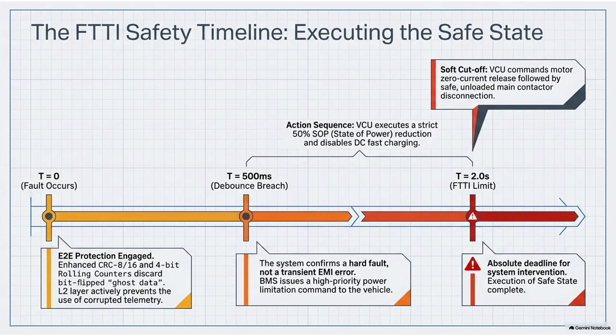Exactly. In milliseconds, the inverter stops chopping the power, and the massive river of current slows to a trickle and then hits 0 amps. Only then, once the current is verified to be near zero, does the system send the command to physically open the high-voltage relays. And because there is no current flowing, the metal plates separate smoothly. No arc, no fire, no damage. The high-voltage system is safely isolated.